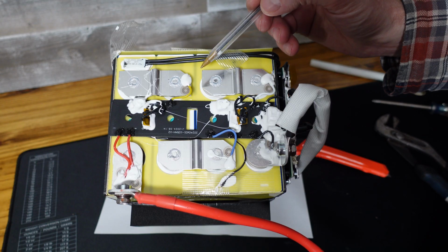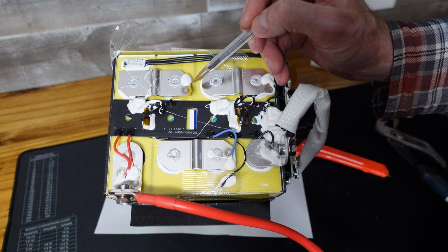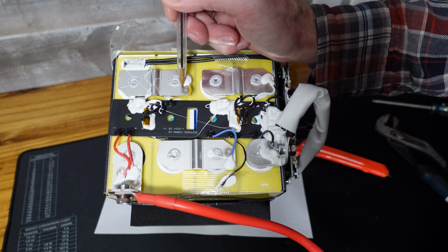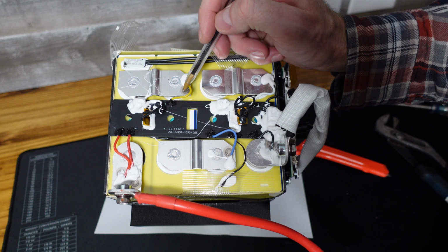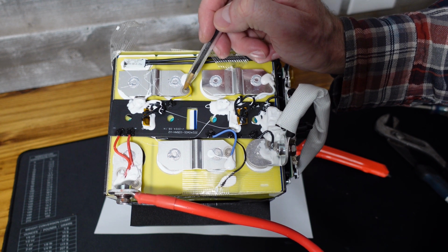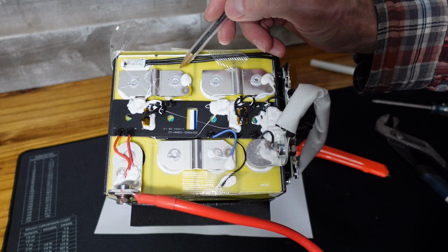And then the last thing I'm taking note of here is how the balance leads are affixed to the bus bars. They appear to be laser welded, perhaps aluminum tabs, or I guess it could be a nickel tab, some sort of non-aluminum material there, which the balance leads are then connected to.